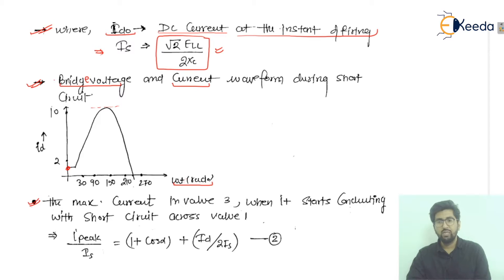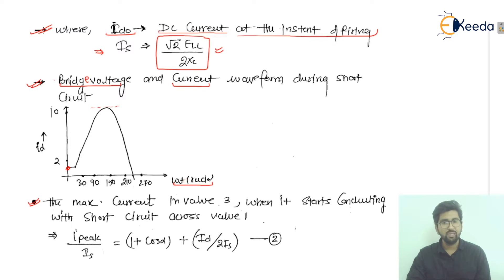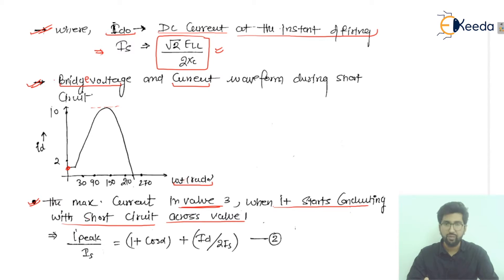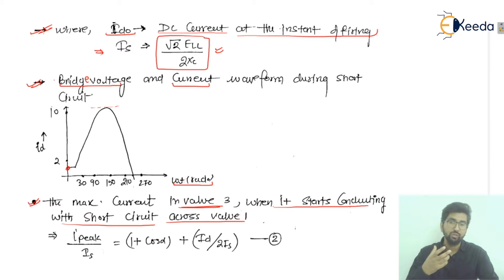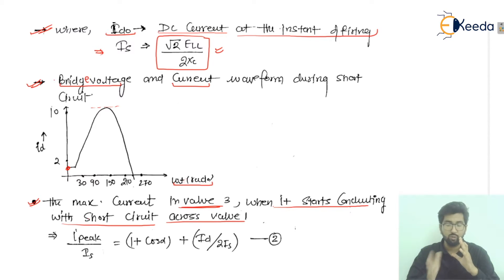The maximum current in valve number three — taken here for analysis — occurs when it starts conducting with a short circuit across valve number one. As seen in commutation failure, there is a transfer of current from valve one to valve three. In the upper commutation group, the sequence is: one, three, five, operating after each 60-degree interval. The commutation goes from valve number one to valve number three.